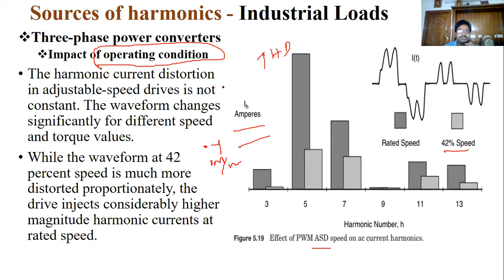The motor is at zero at starting. For suppose in a packing industry, at one instant the motor is stopped, and at another instant it goes on. You remember, on and off cases are continuously running with different speeds. The amount of current drawn by the load changes, and based on that, the harmonics injected into the system also change.